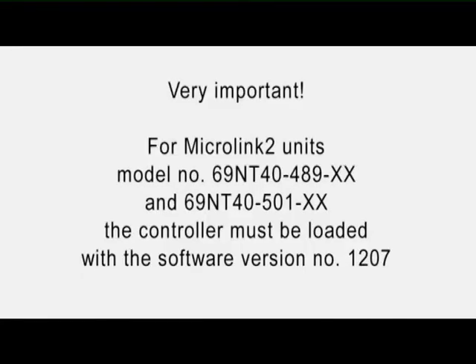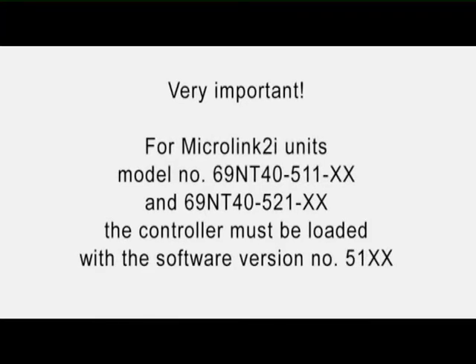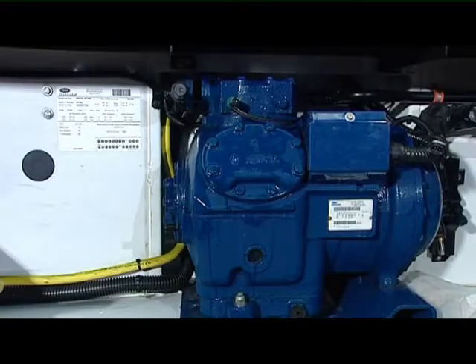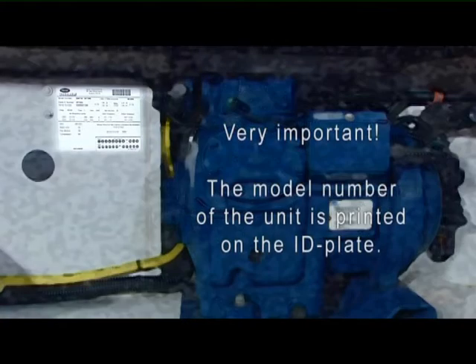Very important. For Microlink 2 units, model number 69NT40489 and 69NT40501, the controller must be loaded with the software version number 1207. For Microlink 2i units, model number 69NT40511 and 69NT40521, the controller must be loaded with the software version starting with number 51. The model number of the unit is printed on the identification plate.